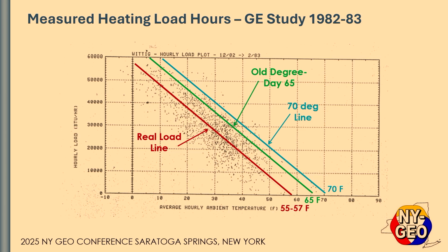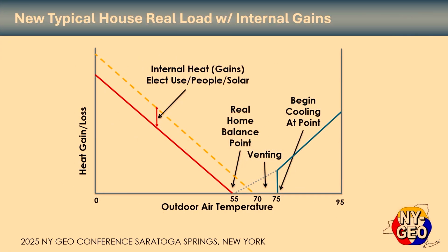So what this is trying to say here is where it crosses the axis there at 55 degrees, that's where you actually need heat in the home. Above 55, you don't really need heat in the home, and that's because of internal gains, solar gains, electric use, all of that wraps up into internal gains. This is an important part when you're trying to calculate annual energy use, but it's not really a peak, and I'll talk about that a little bit later on.